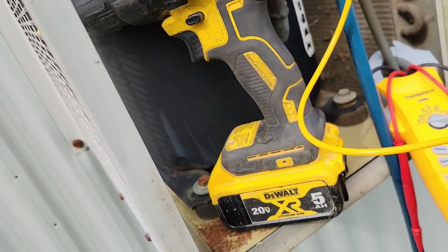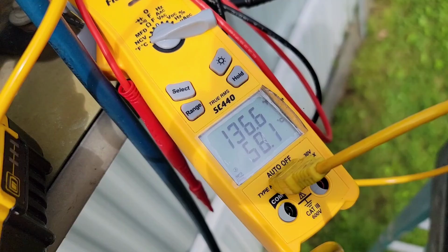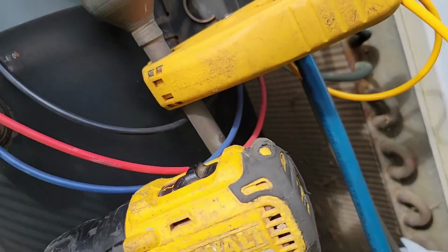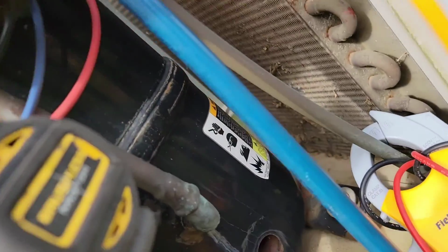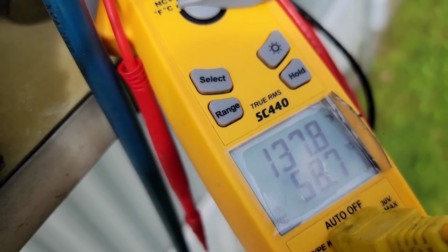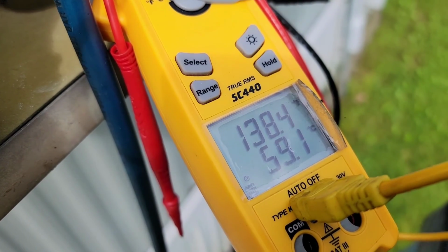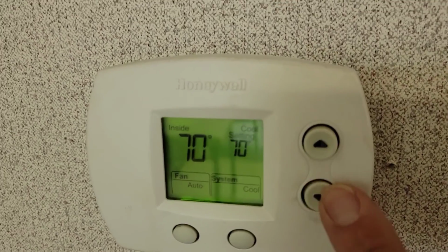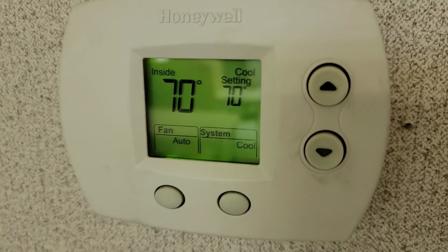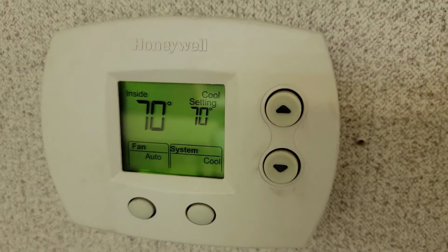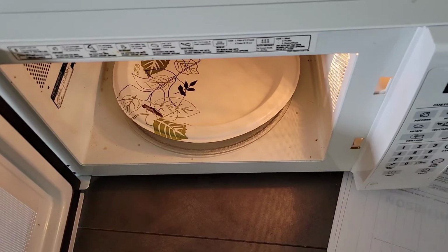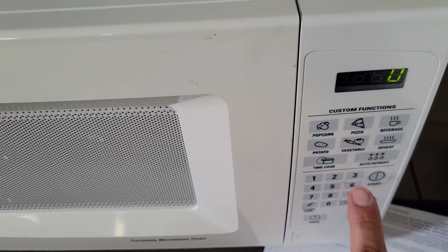Now let's add refrigerant. Discharge temperature is 137. We're on the discharge line of the compressor now. 138, 140. Always check your filters, make sure your coils aren't super dirty. I can't turn the thermostat below 70 for cooling. So what do? All right, I got a little trick for this. Paper plate, napkin, microwave.